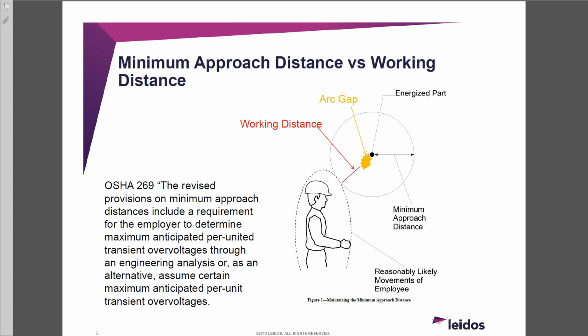The confusing part about the OSHA 269 is that what safety apparel this guy has to wear is based on this distance, because it's claiming that if he does any work on the energized part, like with a stick, like a hot stick or something, that the true incident energy value is from this part of the arc gap. So this distance is shorter than the minimum approach distance. And this is where I'm trying to link it all together here.